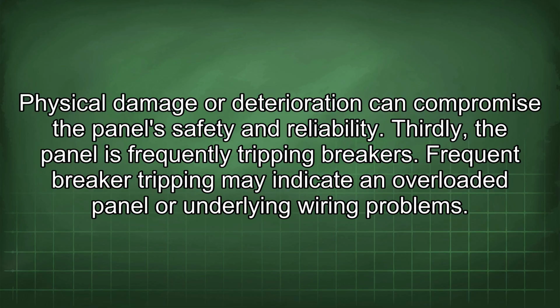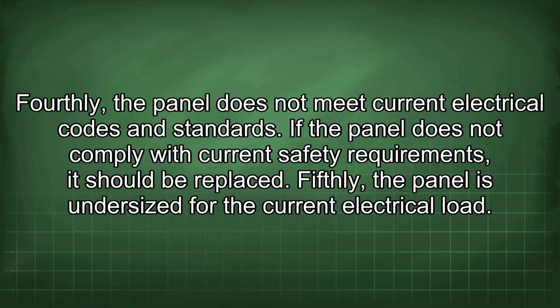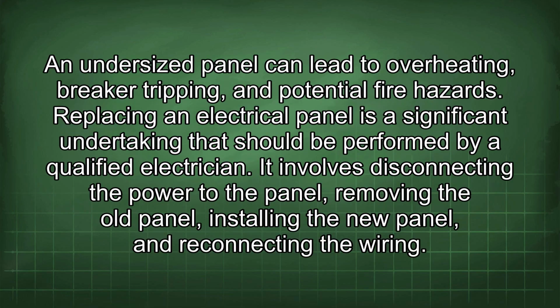Thirdly, the panel is frequently tripping breakers. Frequent breaker tripping may indicate an overloaded panel or underlying wiring problems. Fourthly, the panel does not meet current electrical codes and standards. If the panel does not comply with current safety requirements, it should be replaced. Fifthly, the panel is undersized for the current electrical load. An undersized panel can lead to overheating, breaker tripping, and potential fire hazards.